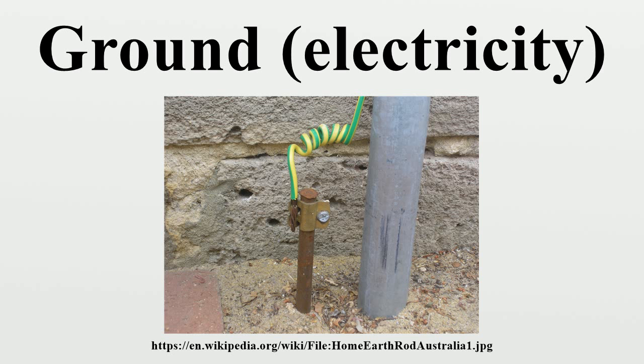An electrical ground system should have an appropriate current carrying capability to serve as an adequate zero-voltage reference level. In electronic circuit theory, a ground is usually idealized as an infinite source or sink for charge, which can absorb an unlimited amount of current without changing its potential. Where a real ground connection has a significant resistance, the approximation of zero potential is no longer valid. Stray voltages or earth potential rise effects will occur, which may create noise in signals or, if large enough, will produce an electric shock hazard.